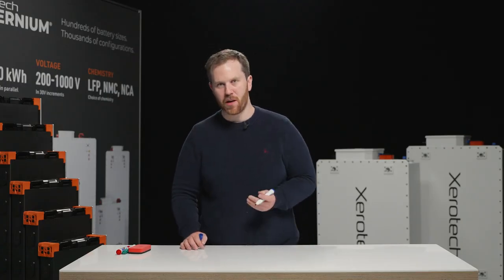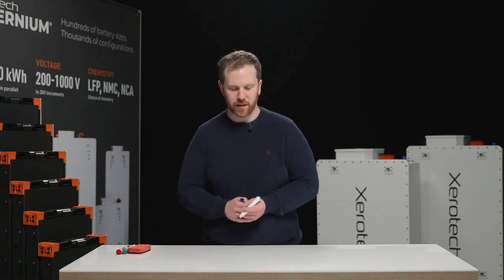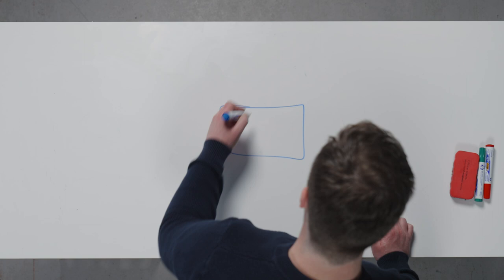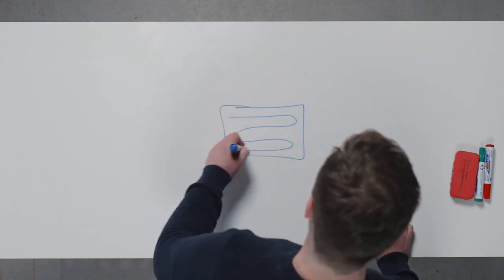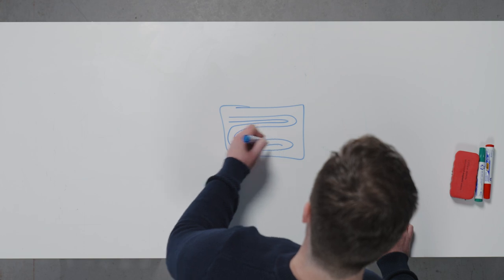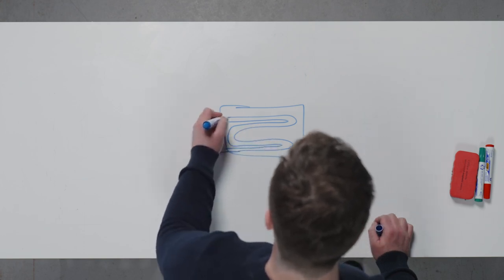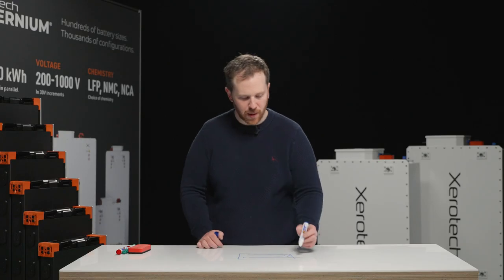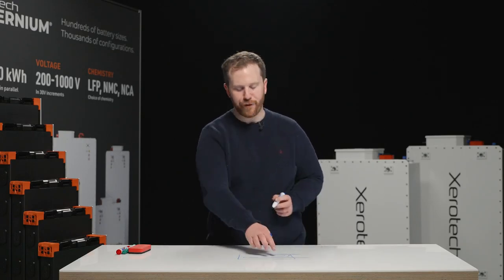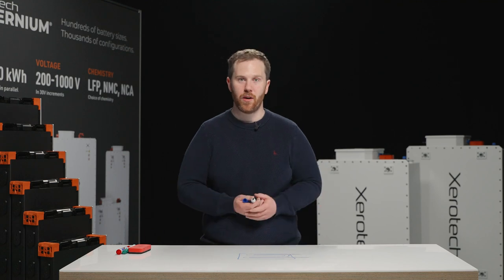So the other important thing to look out for when you're commissioning a Xerotech battery is the coolant fill procedure. So within all Xerotech batteries, there are inflatable plastic ducts. This is a very unique technology that's different to all other heat exchangers in one key regard. So virtually all cooling systems in the automotive world have a standard coolant fill process. So if you've got a battery that's got a bunch of pipes of some description inside of it, you want to make sure that there's no air left in the system. And the way this is typically achieved is that you apply a vacuum to the system, basically suck all the air out of the system.